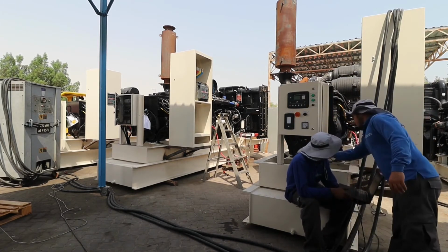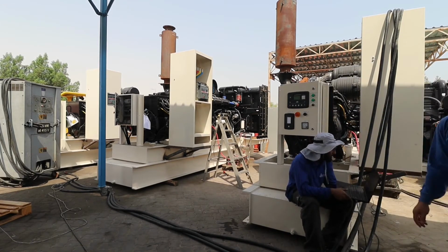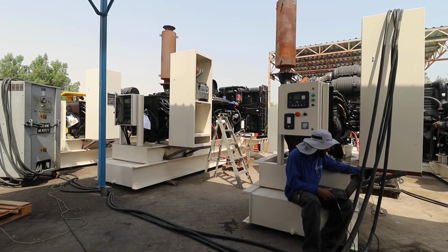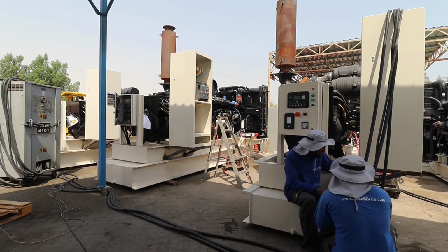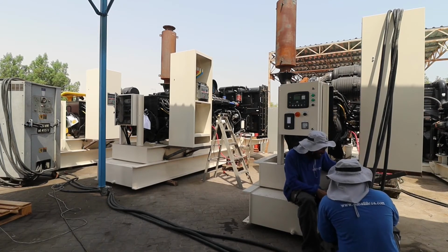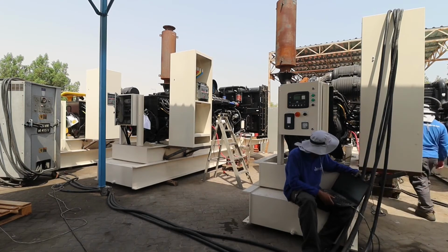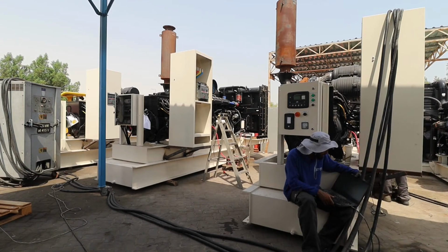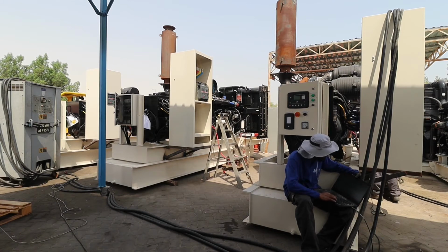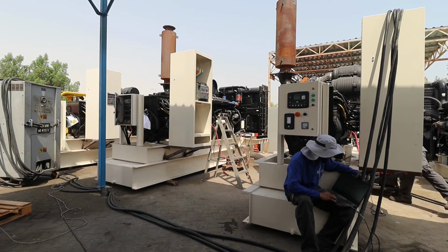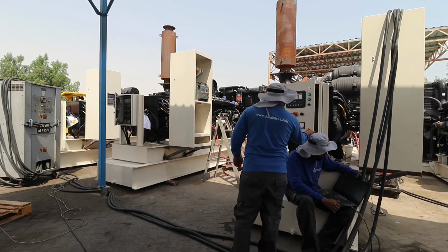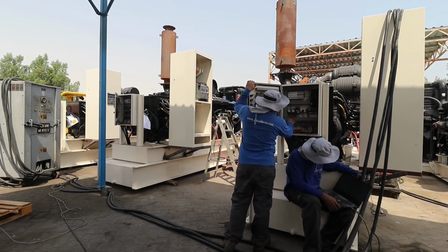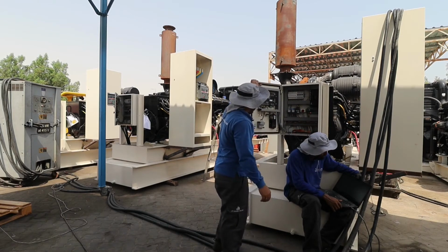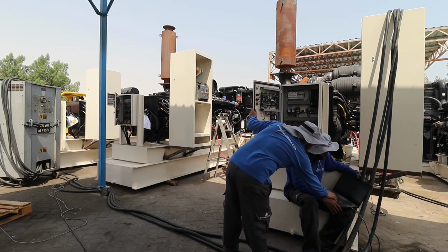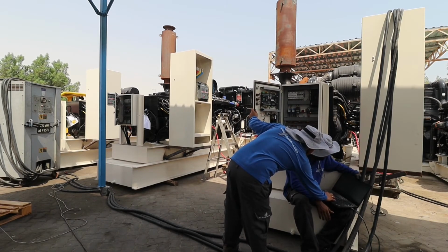If in case that it's not communicating, meaning there is no supply going to the ECM, probably that is the problem. And check again why it's not communicating. So I just tightened our ECM connections a little bit. So now I powered up only the breaker for our supply for the ECM. Why is it still not communicating?